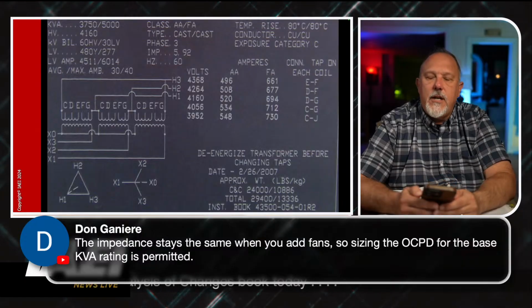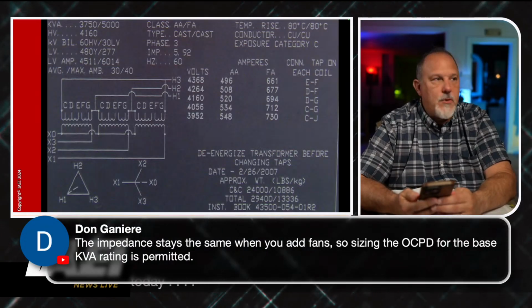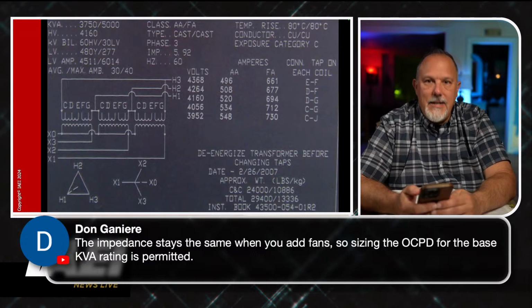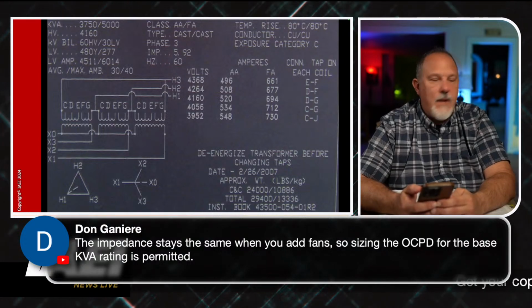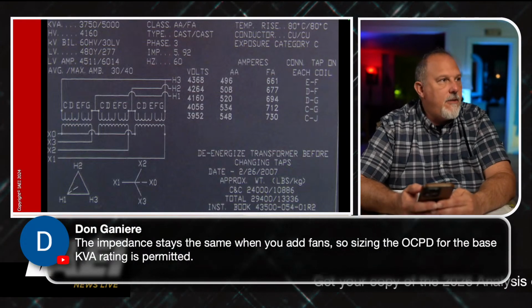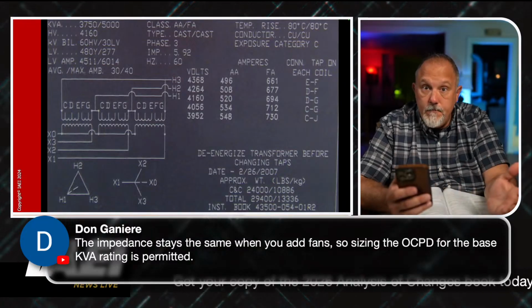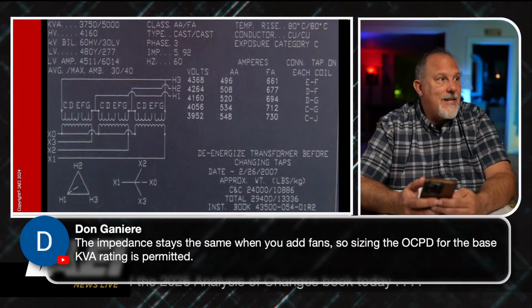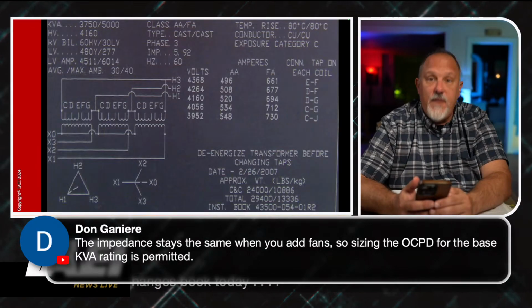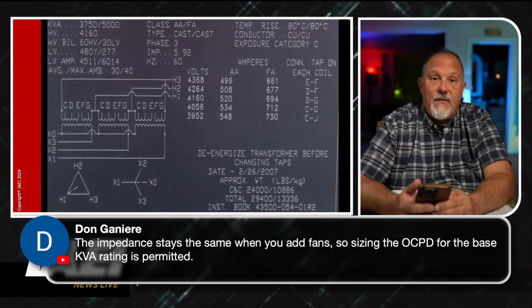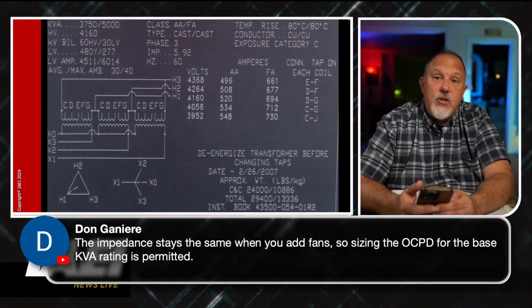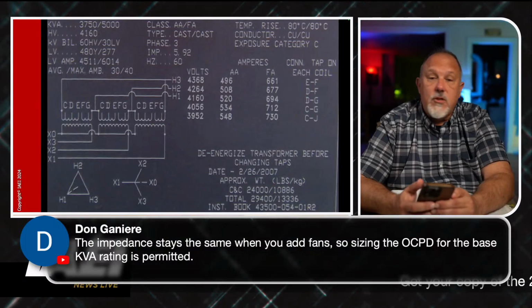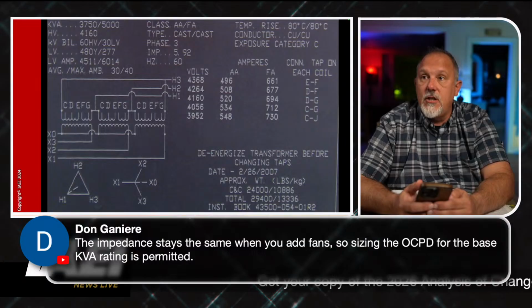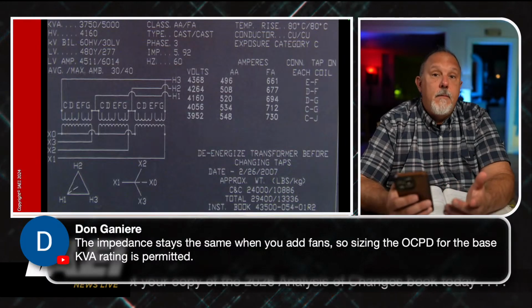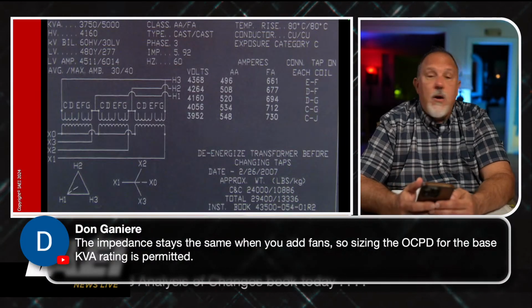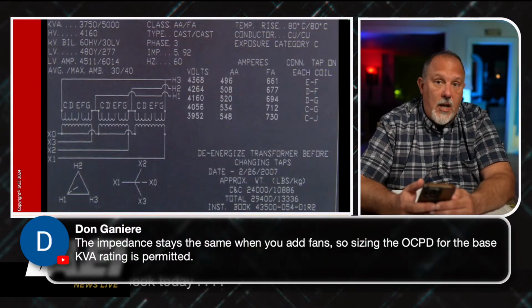If I'm medium voltage, I don't have the 80% issue. It's all 100%. So I have to at least make sure my primary overcurrent device will permit 694 amps to flow. If I have an overcurrent device that's less than that, it may work on the 3750 kVA, but it's not going to work on the 5000 kVA. I don't care about the short circuit protection, because to your point, the short circuit protection is the short circuit protection. But it's the overload that I'm worried about. I'm not worried about inrush because inrush is not going to change.